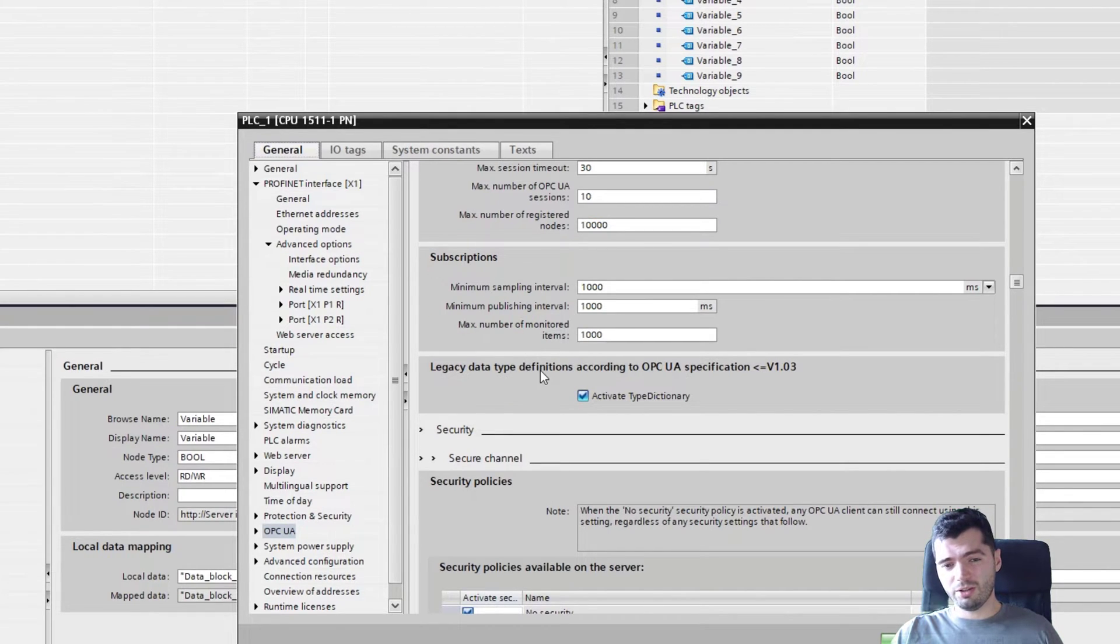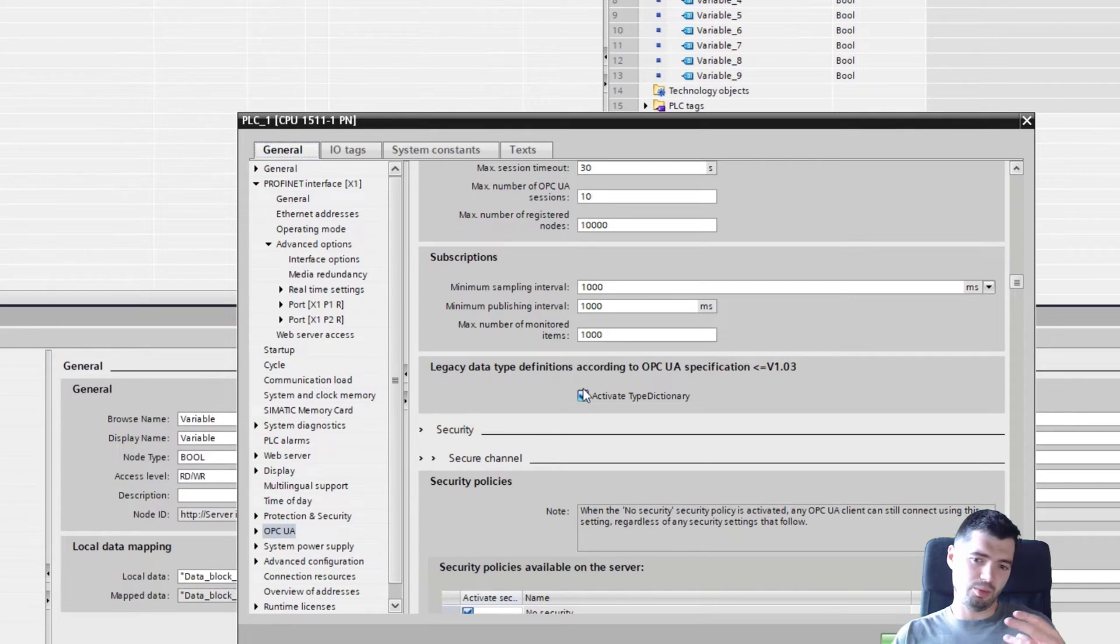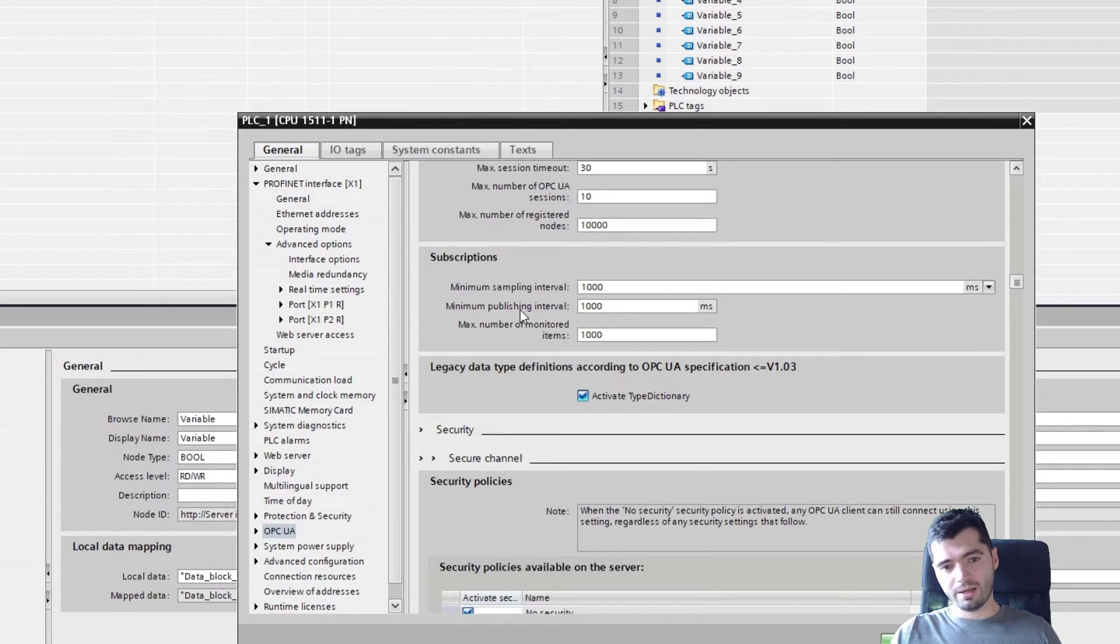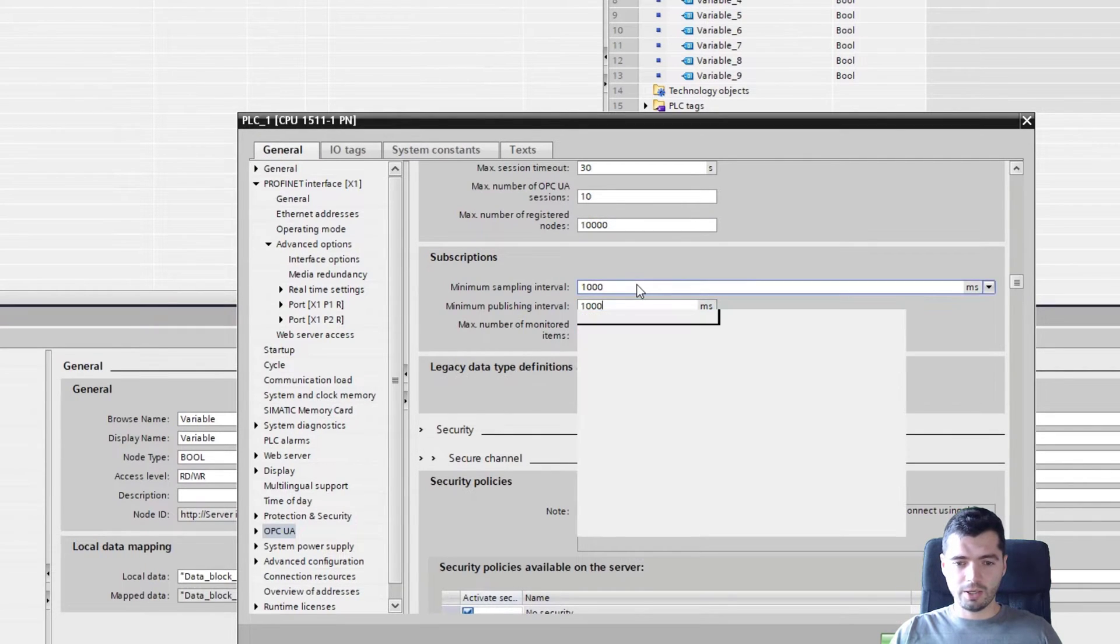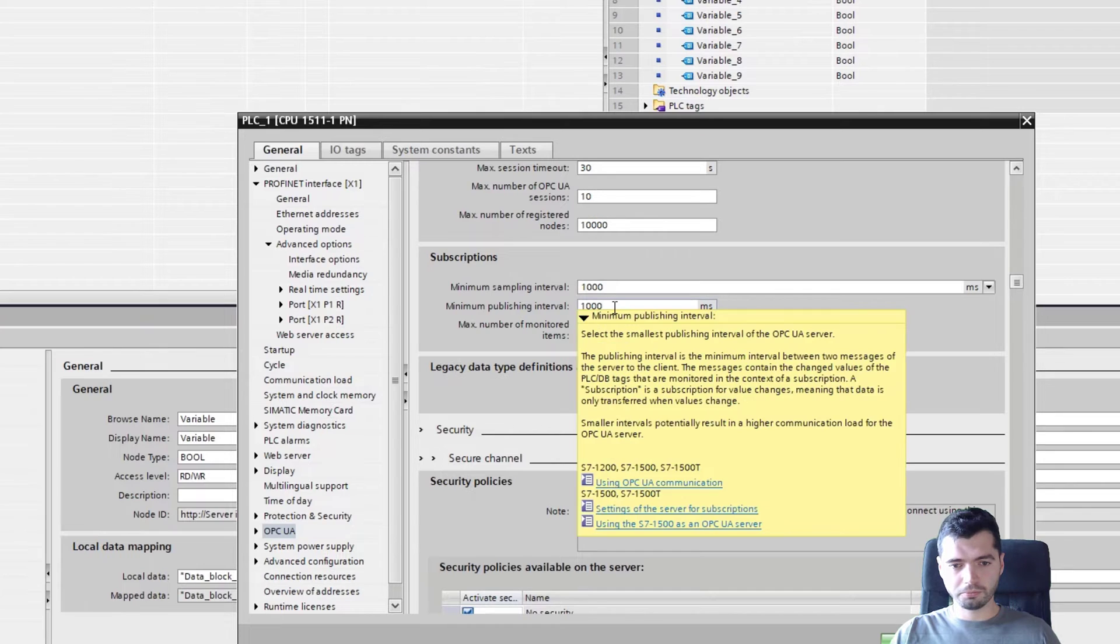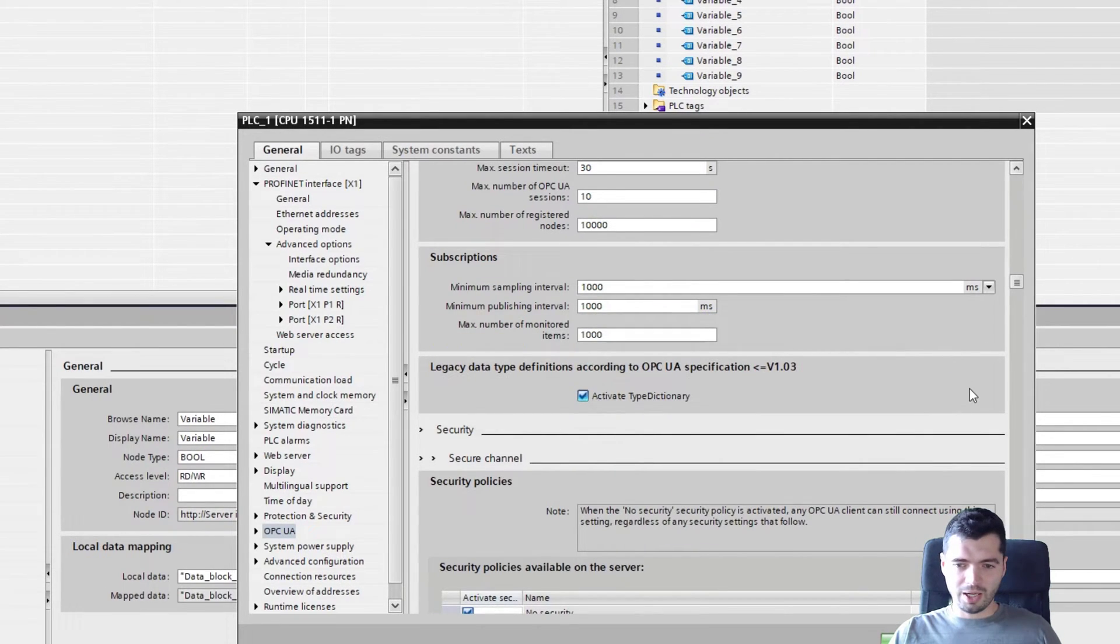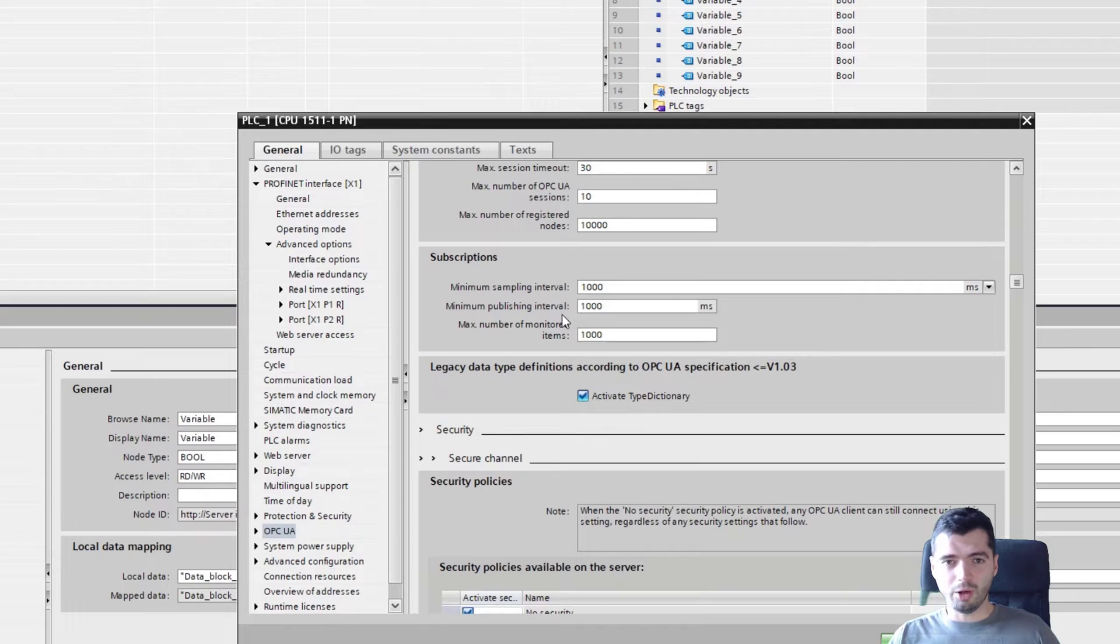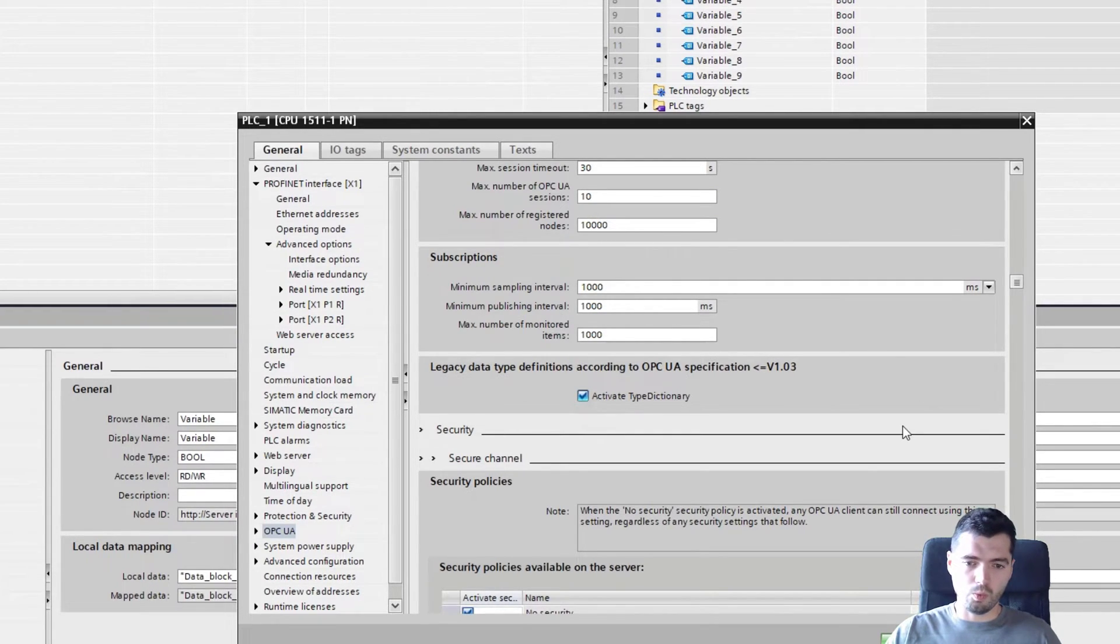The sampling and publishing intervals are quite interesting things because sometimes you are interested in doing registered reads. You set them to be, let's say, 200 milliseconds, but it doesn't work for you. Why it doesn't work? Because the minimum intervals set here are above this value. And you can, if you actually hover over this and hit F1, this will give you a detailed explanation of what this is and how to change it. Just to be wary, these things have to do with the registered reads, not the normal reads, and might be preventing you from achieving low read intervals and you might need to adjust these settings if you want to go below one second.